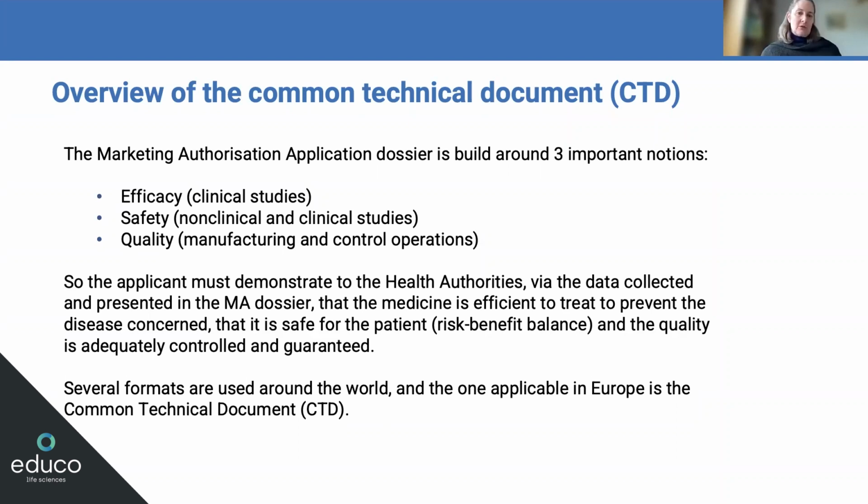You need also to demonstrate that it is safe for the patient, and this is the risk-benefit balance, and that the quality of your product is adequately controlled and guaranteed. And you actually have several formats around the world that are used to submit those kind of data, and the one that is applicable in Europe, but also in the ICH region, is the CTD, the Common Technical Document.